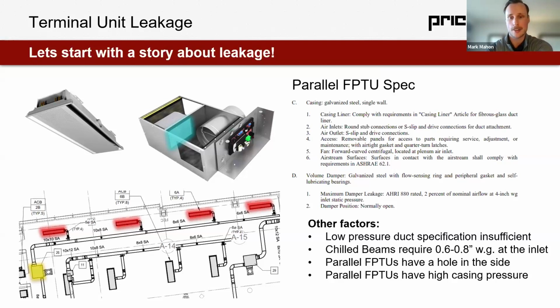And so we have a number of factors here: a higher pressure system, a low pressure duct specification, which is insufficient, seal class C only, a very low leakage class for the ductwork as well. We have a parallel box with a hole in the side. Traditionally, parallel boxes have higher casing leakage. We're now in a scenario where this project has been built and is going through commissioning. We don't have the plus or minus 10% airflow we need, and Price as a manufacturer fully complies with the spec and never even really interfaced with the project until it was built.